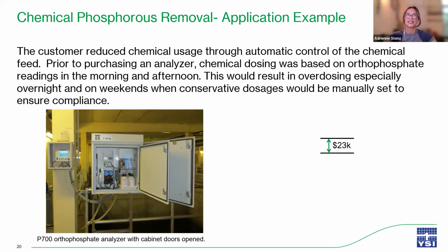This is a case study done at a facility in Wisconsin, which saw significant savings on the cost of chemicals for chemical phosphorus removal by implementing an orthophosphate analyzer. Prior to the analyzer, operators were manually dosing ferric chlorides based off of phosphate grab samples, which they took twice per day. Operators would dose large amounts of chemicals to be conservative and to ensure that their effluent phosphorus limit of 1 milligram per liter would be met.